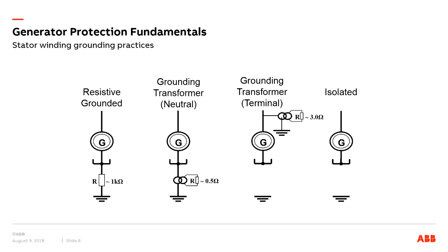And the third one is having a grounding transformer at the terminal side. So here you can see that the grounding transformer is connected to the terminal side. This transformer is a Y delta connected transformer with the neutral point directly grounded, and the secondary side of this transformer is connected in broken delta with a resistor across it. The value of this resistor is in ohms, with a typical value of about 3 ohms. The secondary winding voltage typically is about 500 volts.